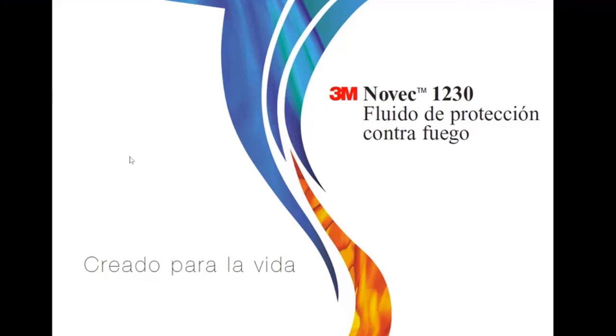Usually we can go 80% longer on piping runs with 500 psi. For example, last week we had a project in Costa Rica where the only place to put the cylinder was 30 meters from the room. Other competitors couldn't do it, but we can do it with 500 psi. And the cylinder, nozzle, and everything costs the same as a regular pressure system, so it's no big deal - they don't have to pay more, and we can do something with our system that our competitors can't.